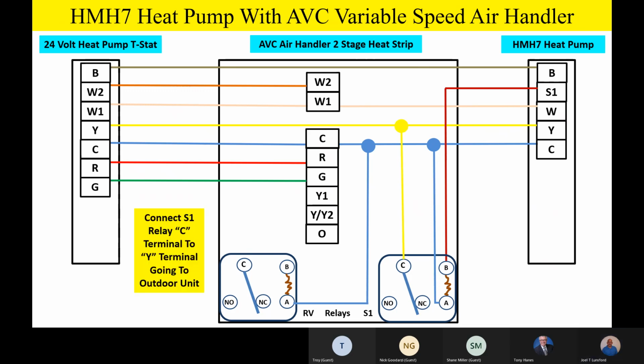We're going to take the common terminal of the switching contacts and hook that up to W. To hook that up to Y, just like we had before. The common of the switching terminals goes up to Y, just like we had before. So anytime we have compressor operation, we'll have voltage on the common of the switching terminals. The normally closed contact on the S1 relay goes up to Y/Y2 for high-speed airflow. The normally open contact on the relay goes up to Y1 for low-speed airflow.